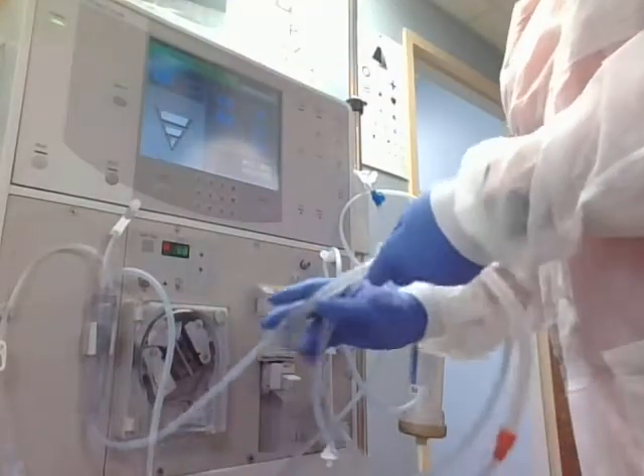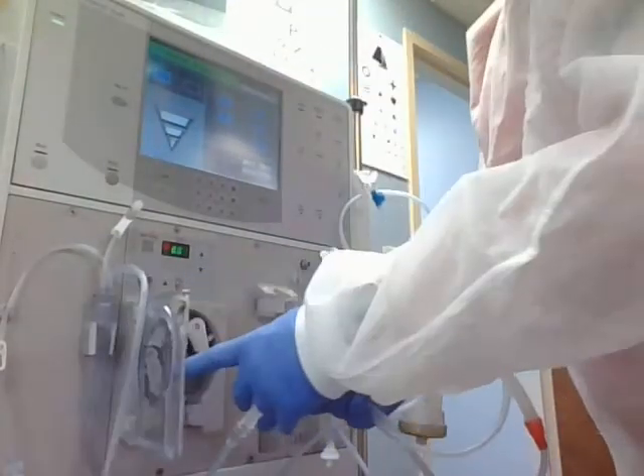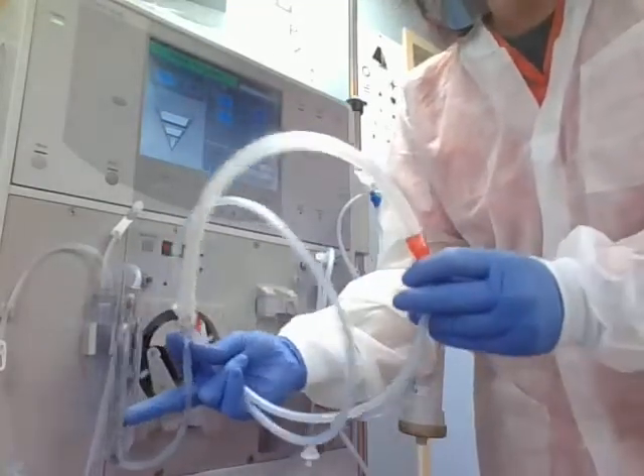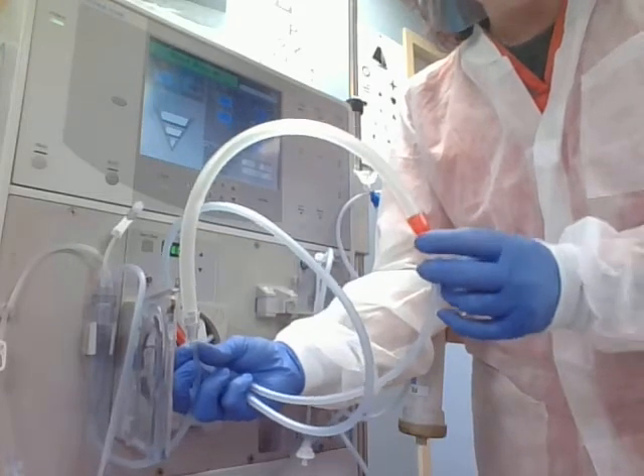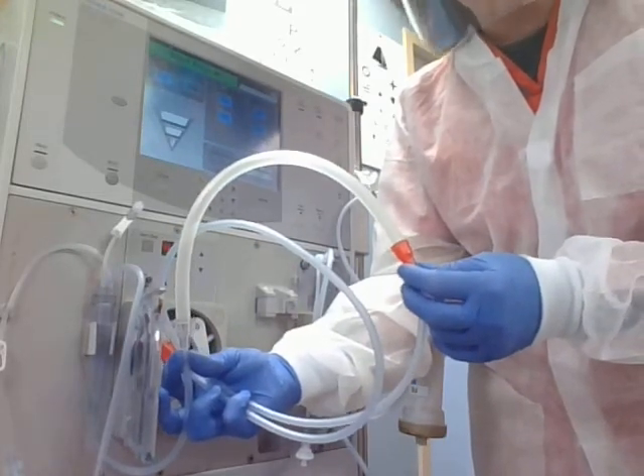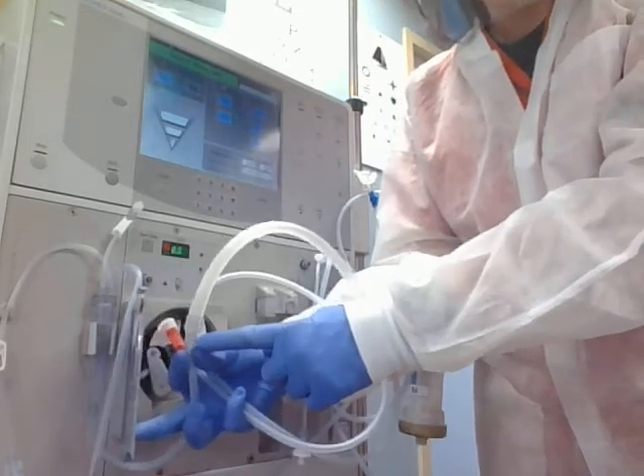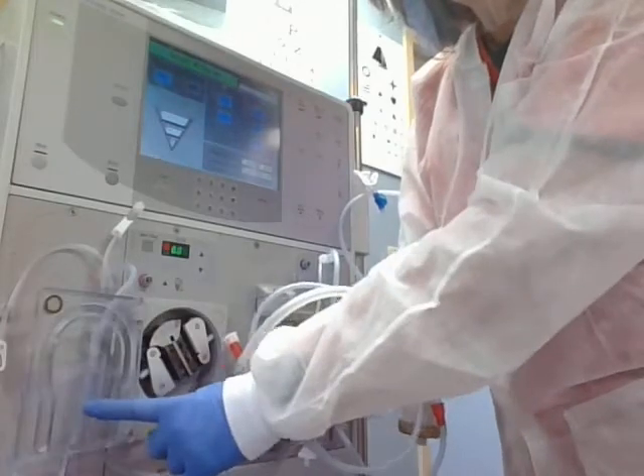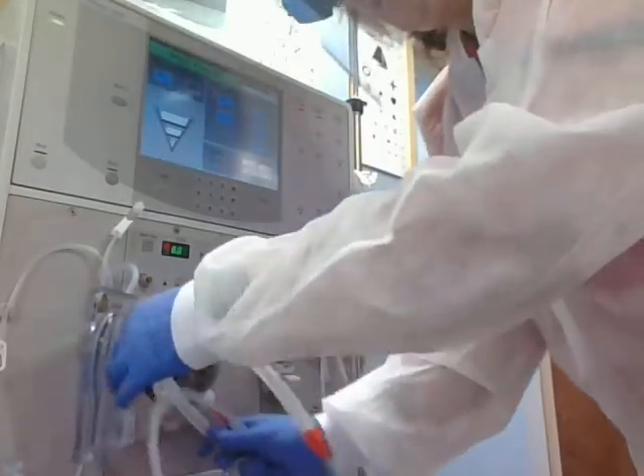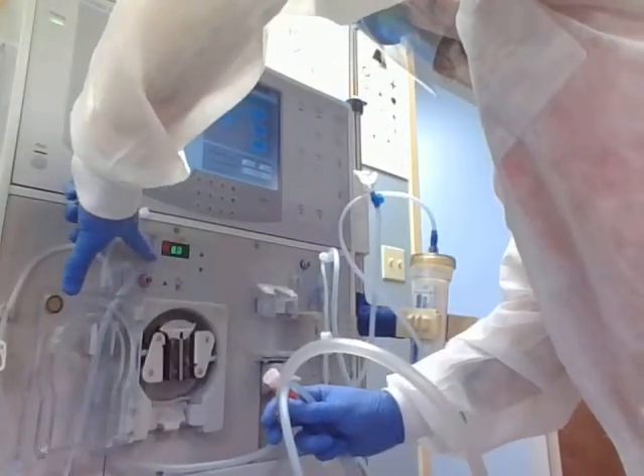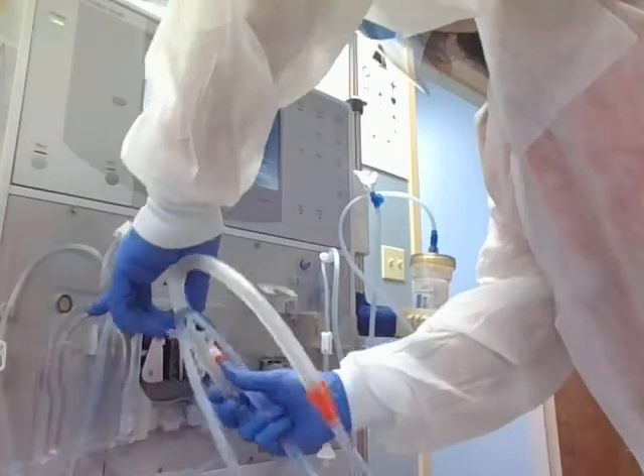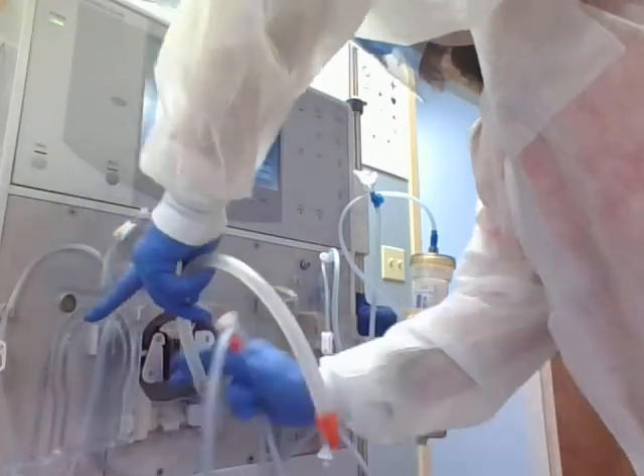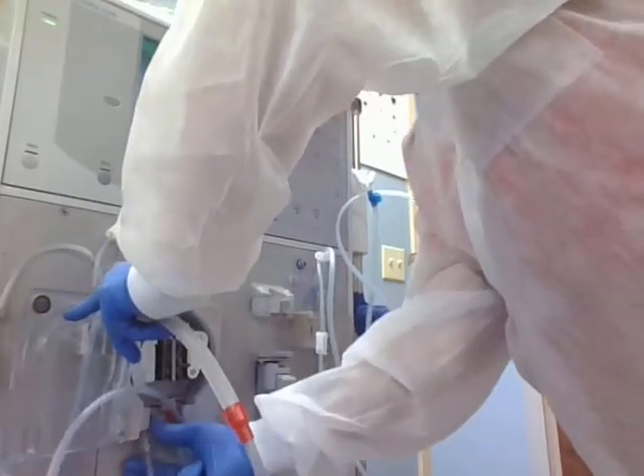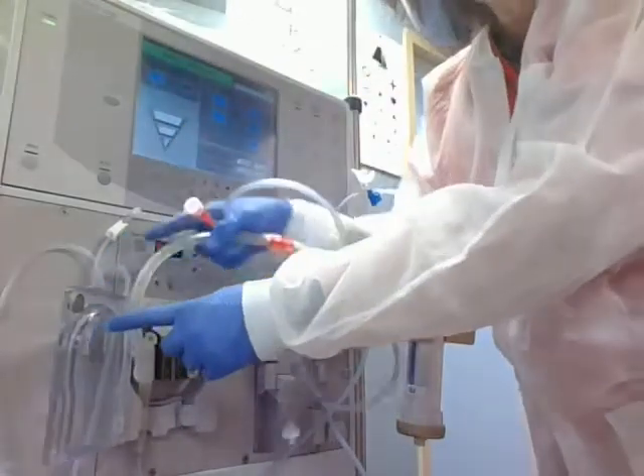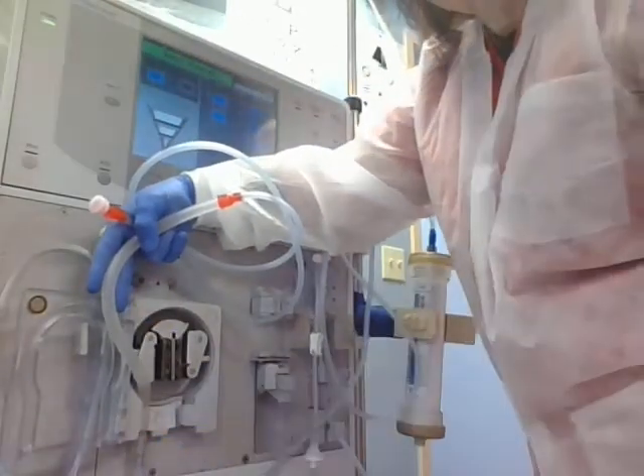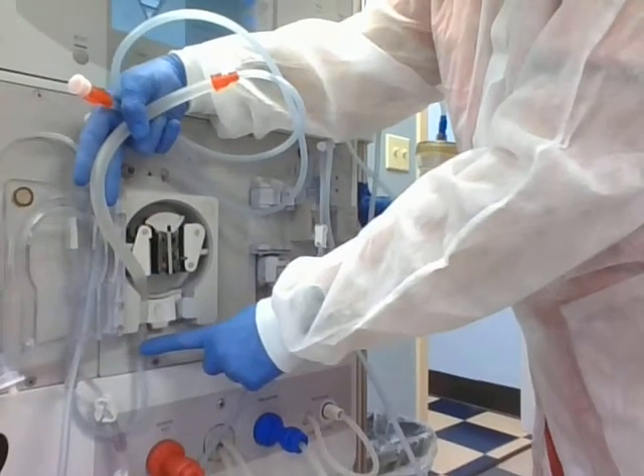This, I'm going to take that tab off. On your blood pump tubing, it has 2 ends. Notice that only one end has a color on it. This is your exit end. This is the end that goes at the end of the blood pump. The clear part goes in first, in the first part of your blood pump. All right, so we're going to move our blood pump forward, and the way that we do that is just press your little start button here. It moves your pump head forward just so you can get this in. And you want to take this and push it in all the way, make sure it is fully seated. Notice again, this is the clear part. This is the one with the clear part on the end.